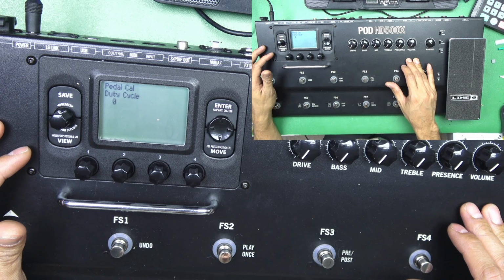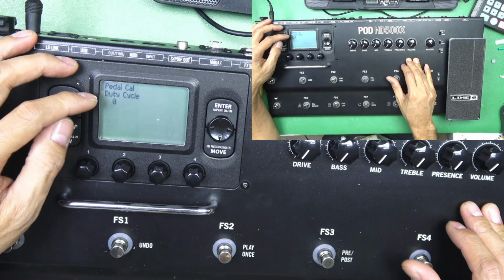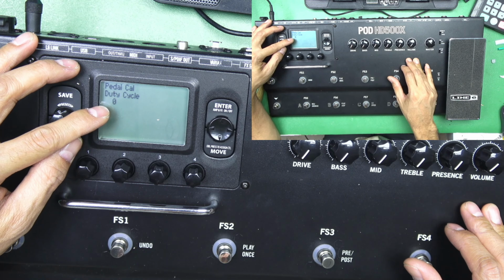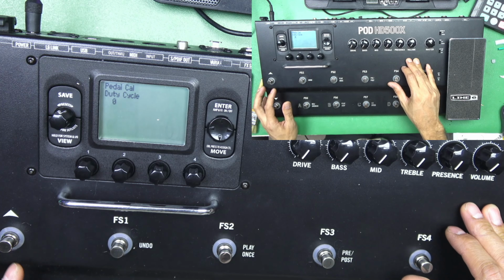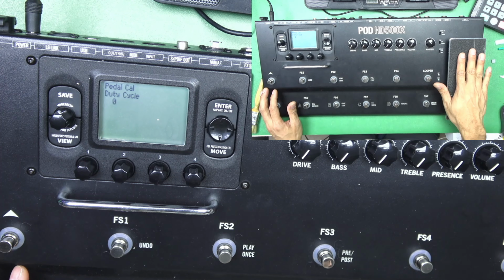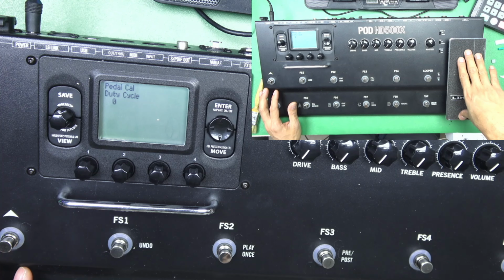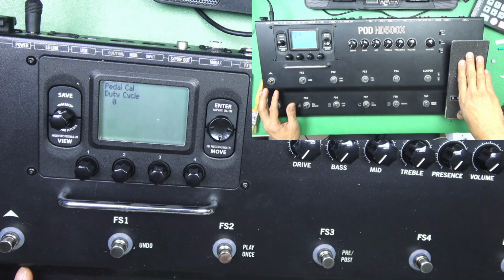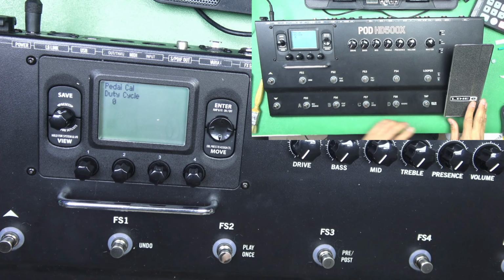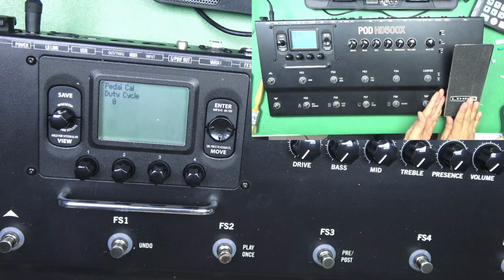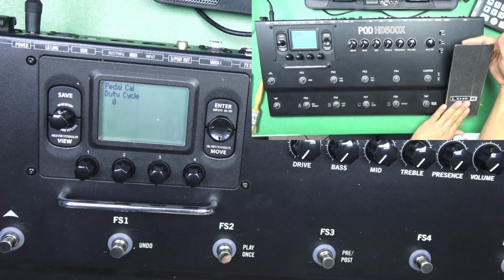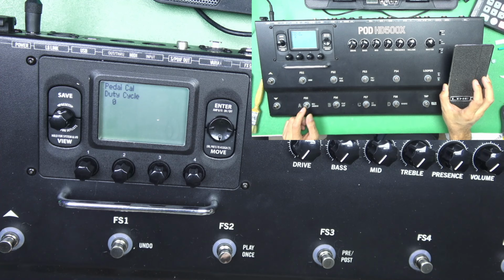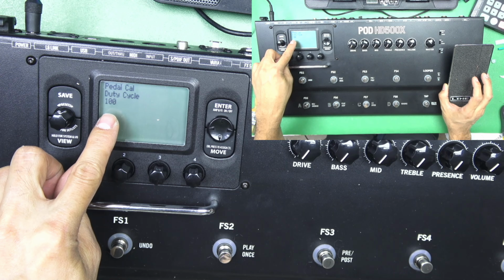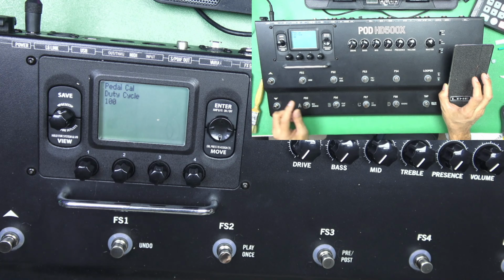one press only, and now the display is pedal calibration duty cycle, which is 0. Now we have to go to the pedal. The position must be on the heel side. This one is down, this one is up, and then after that we have to press the A button, and then as you can see, the value changed from 0 to 100.